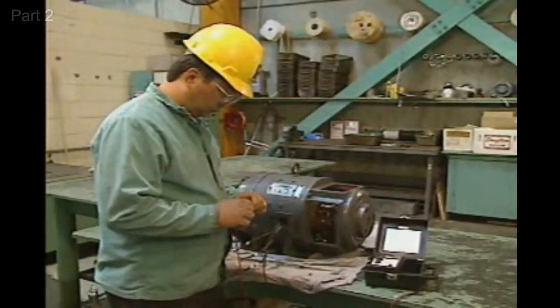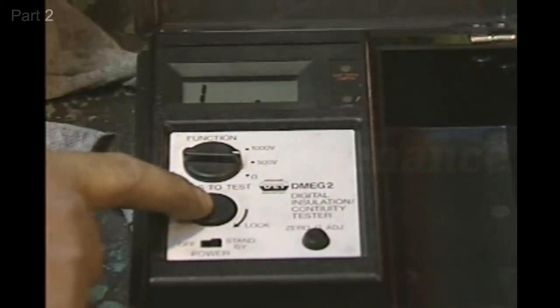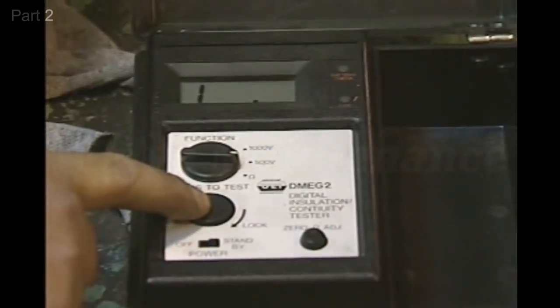Next, separate the probes and operate the meg-ohm meter again. This time, it should indicate infinite resistance. The digital readout on this meg-ohm meter indicates infinite resistance by displaying a blank readout except for the number 1, which appears all the way to the left.